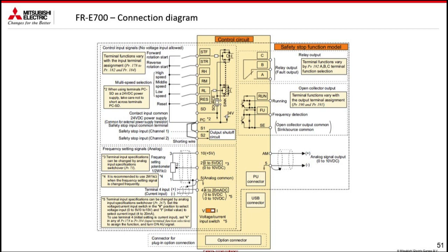As regards the outputs, an output has been added, namely FU, which is an output that is activated, giving me a positive signal when I reach a predefined output frequency of 6 Hz or more. It is usually used to release the brake. I could put 1 Hz so that the motor starts pushing, and then let's go off the brake.